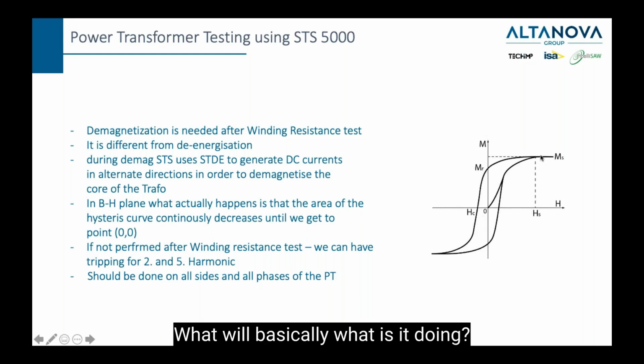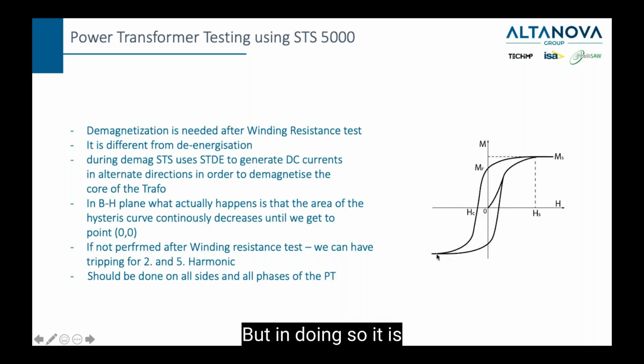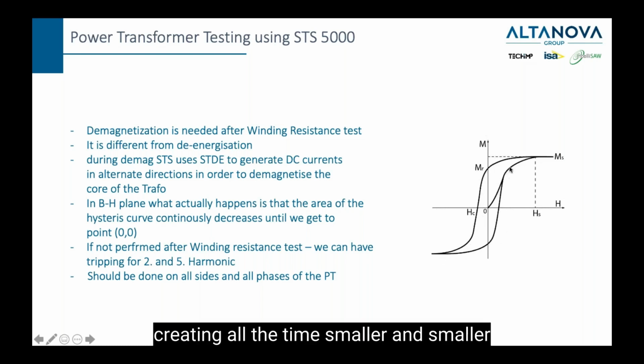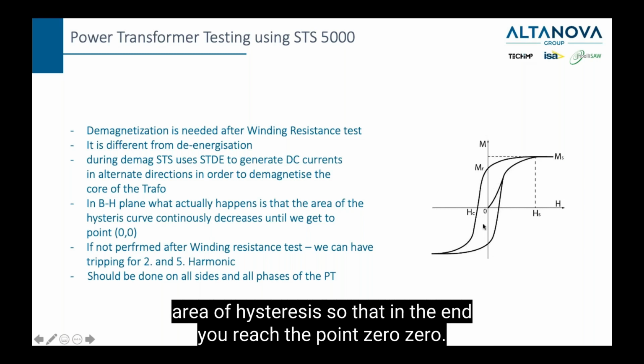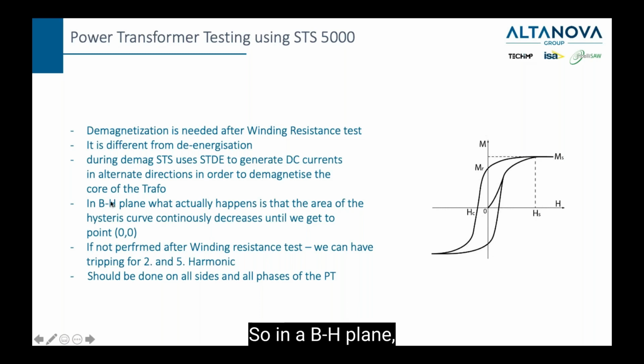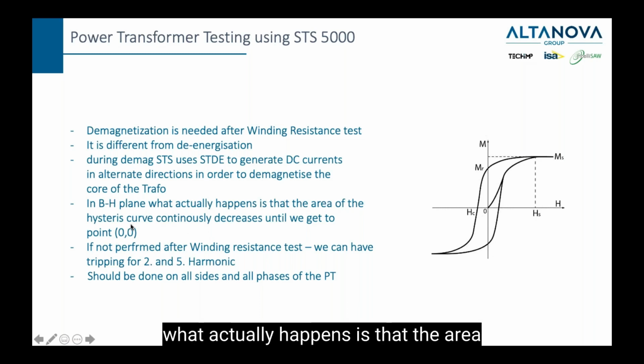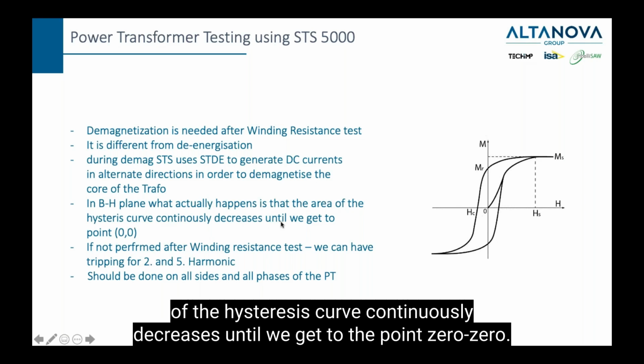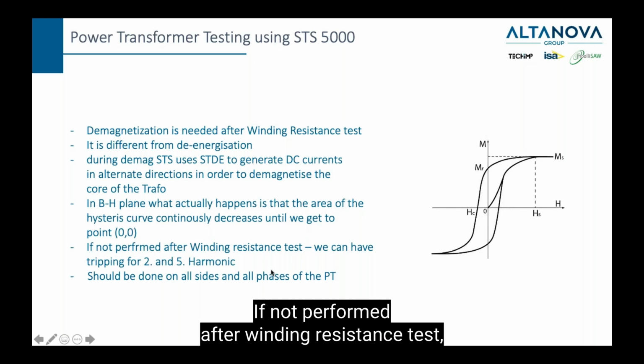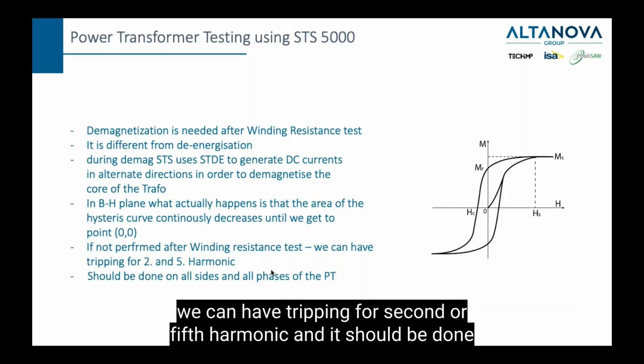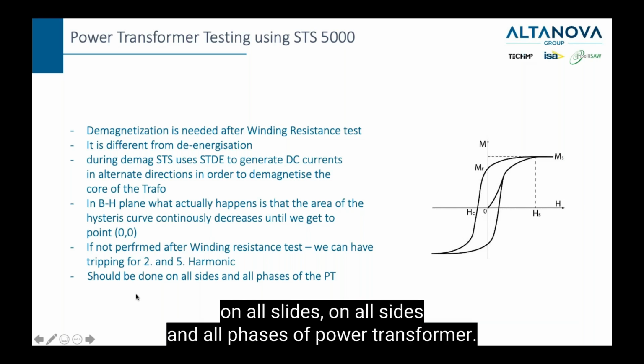What is it doing? In doing so, it is creating all the time smaller and smaller areas of hysteresis, so that in the end you reach the point 0,0. So in a BH plane, what actually happens is that the area of the hysteresis curve continuously decreases until we get to the point 0,0. If not performed after the winding resistance test, we can have tripping for second or fifth harmonic, and it should be done on all sides and all phases of the power transformer.